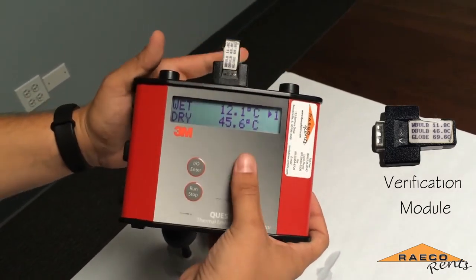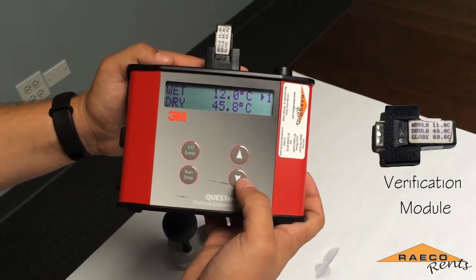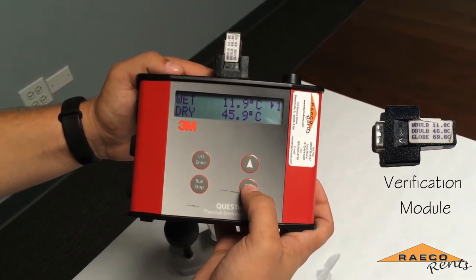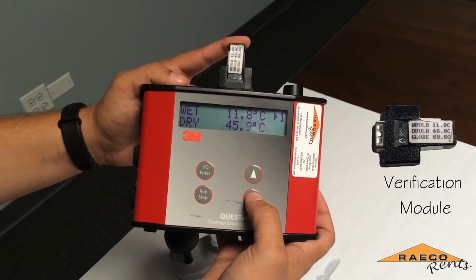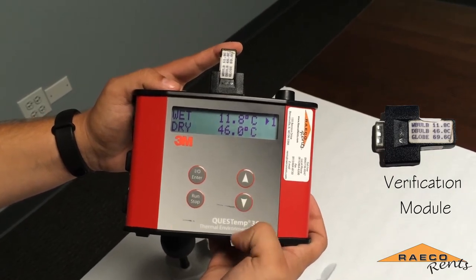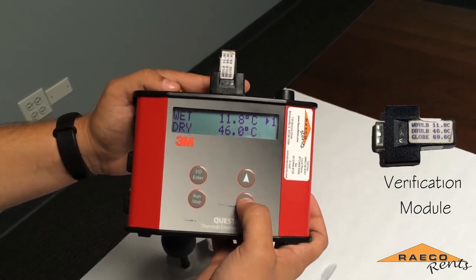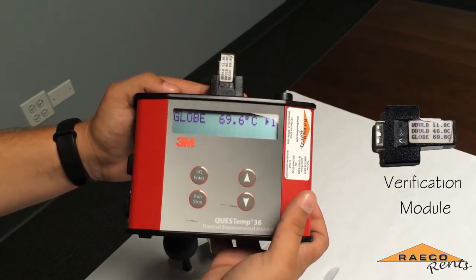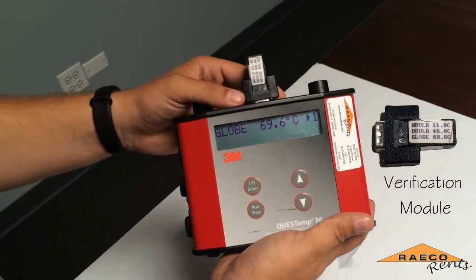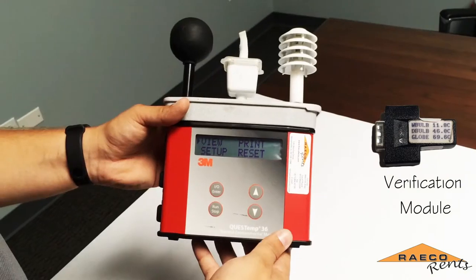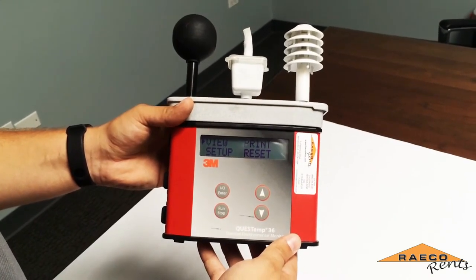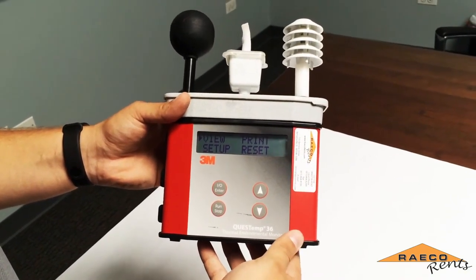If those readings are reflected within the actual measurements and are within 0.5 degree Celsius, then you know it's within calibration. As you can see, this machine is.